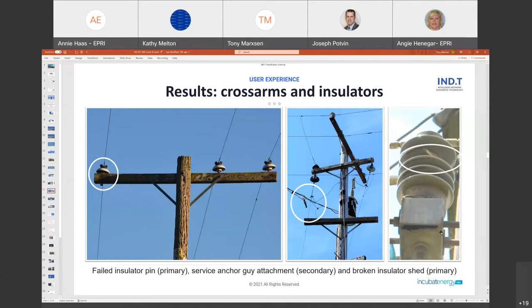The middle photo is again a failed insulator that's pulled out of a split, failed cross arm, which has left the transformer secondary terminals taking the full strain of a very long overhead service line to a customer, about 50 metres. Obviously the strain was producing cracks in the insulators, and we were seeing partial discharge at the transformer.